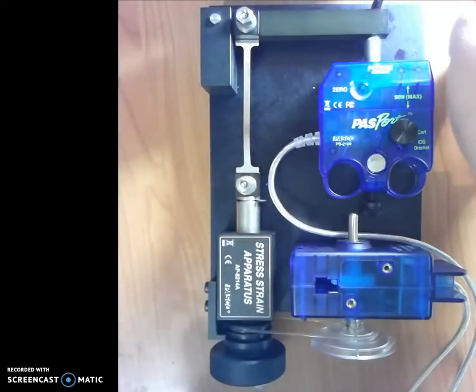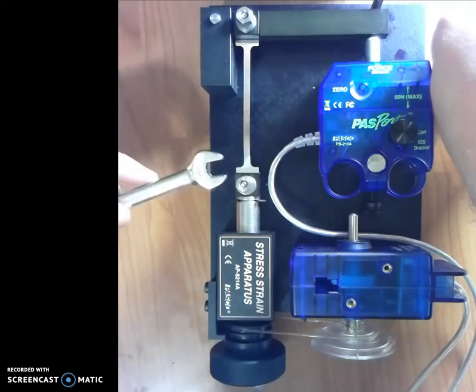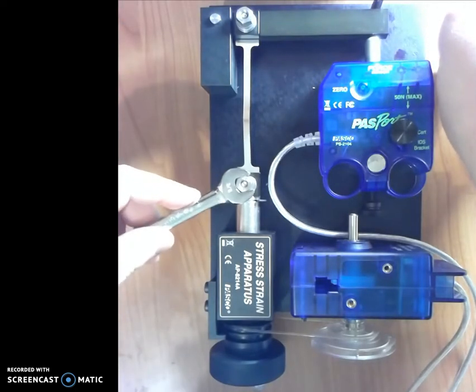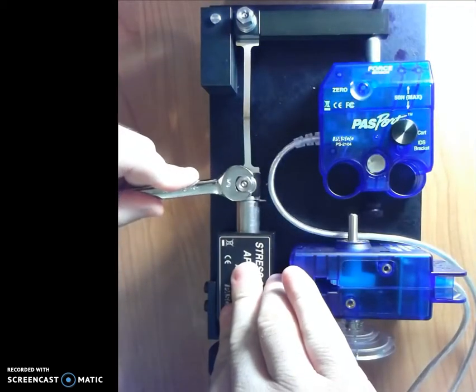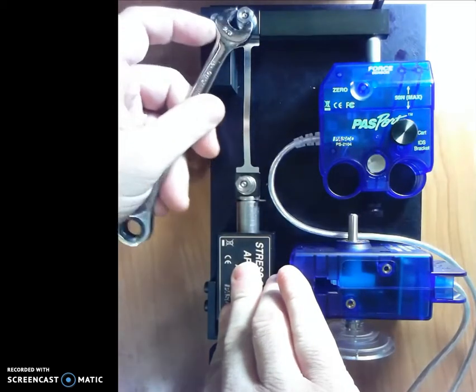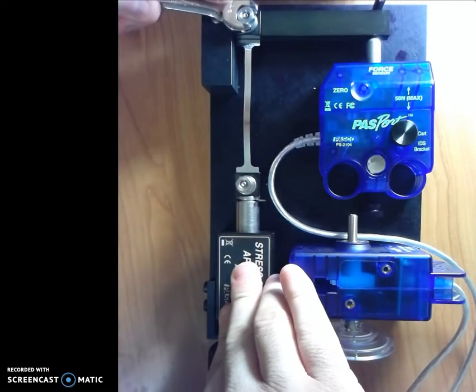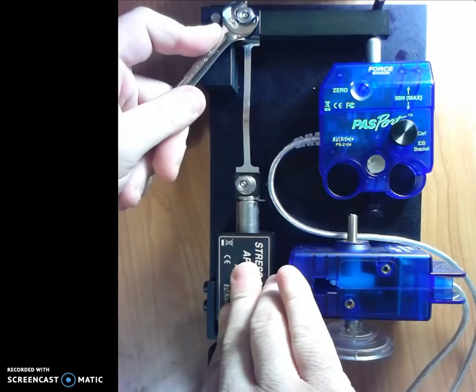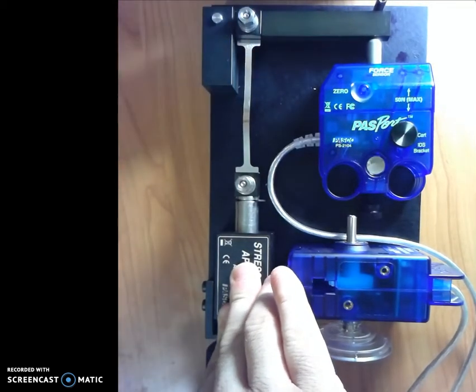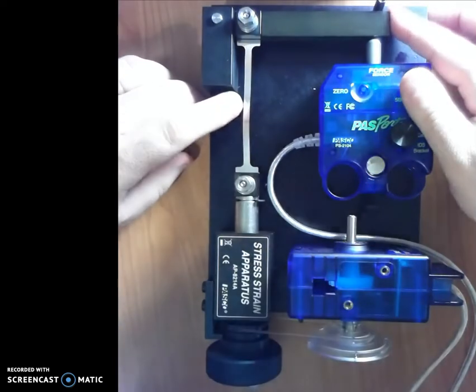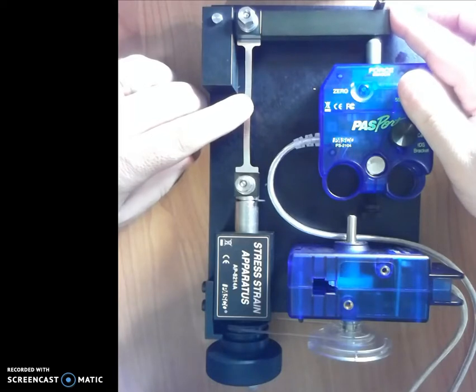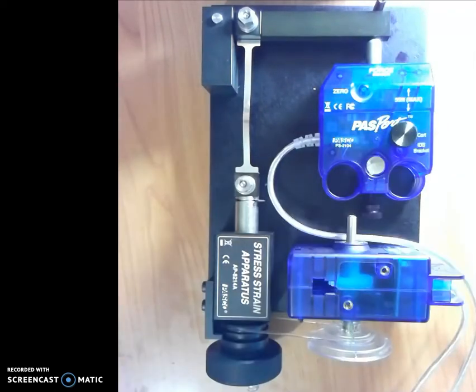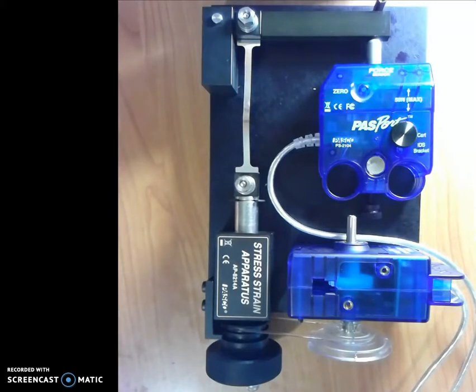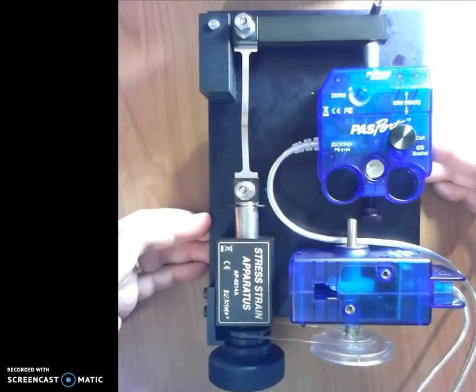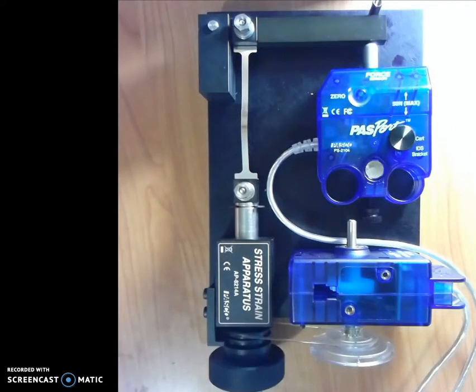Okay, until that's tight. Now, you might not need to do this, but just for completeness, I'm going to take my 3/8 wrench, and I'm going to just tighten things down a little bit more. So that's very tight, and I've got the coupon in, it's not going to slip. Okay, and notice that the coupon does have a little bit of slack here, which is fine because I'm going to have to zero things again like I did before with the calibration bar. So let me move this into view. Okay, so now this is all set up for my stress strain experiment.